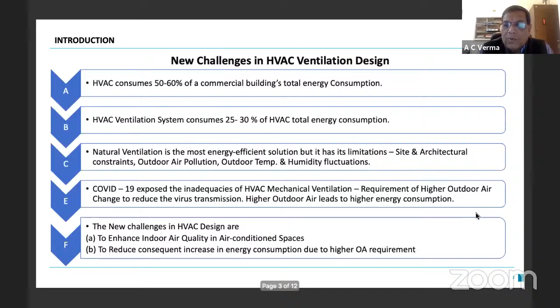So the new challenges in HVAC design are to enhance indoor air quality in air-conditioned spaces, while simultaneously reducing the increase in energy consumption due to higher outdoor air requirements. Presently, this ventilation system is designed on the basis of the minimum outdoor air requirement. That's why, when extraordinary circumstances demanded extraordinary measures like higher and higher outdoor air supply, our systems were not able to match that. This common method is the ventilation rate procedure, laid down in the ASHRAE standard 62.1, and it is common because it is a prescriptive design procedure.